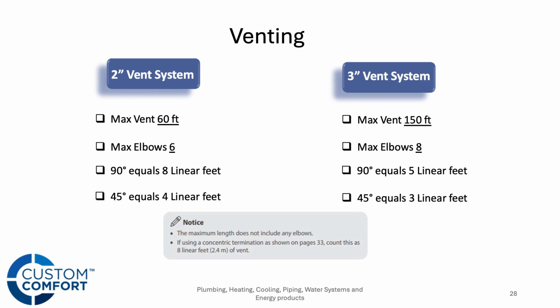And then pretty standard here, but let's talk about total equivalent vent length. Again, 2 inch, we're good up to 60 feet. That's a max of 6 elbows. Every 90 is going to be 8 feet of linear venting. Every 45 is going to be 4 feet. Carry that over to 3 inch, right? Max of 8 elbows. A 90 is going to chew up 5 feet, and the 45 is going to eat up 3 feet of your total vent length there.